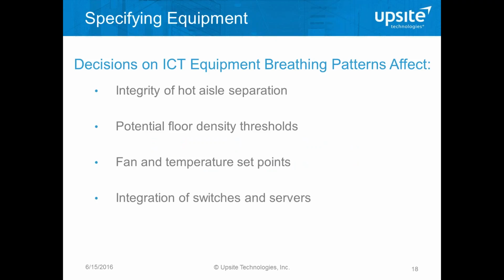Specifying equipment that breathes front to back is another decision that is important that the IT community makes. It has a direct impact on the operation mechanical plan of the data center. This will affect our hot aisle separation. It will affect the density potential of the data center. If we have a lot of equipment in this data center that breathes side to side, that return air contamination in the data center is going to drop the potential capacity or maximum density in that space.